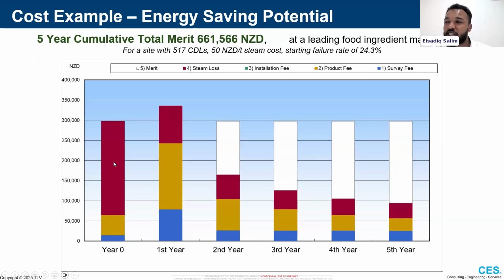So, massive leakage losses. But after implementing steam trap management, the first year has typically high costs because you're replacing a lot of steam traps with typically upgraded models, and the survey costs also hurt you a bit because they're now covering all of the steam traps in detail. However, you can already start to see the leakage losses, that red bar, decreasing massively. And then year on year, you end up with a net benefit. That's taking into account the cost of a survey, a net benefit on this site of well over $500,000 New Zealand dollars.